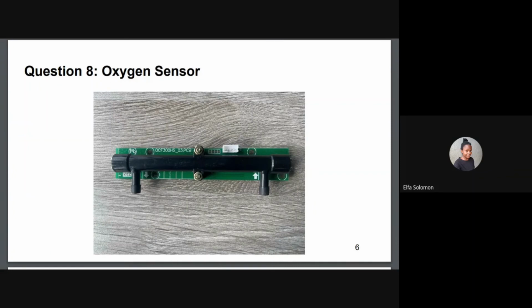That sounds like a sensor failure issue. As we know, oxygen concentrators have sensors installed in them to help enhance their performance and to detect failures within the concentrator. At the end of the oxygen generation system in a concentrator, just before the oxygen is delivered to the patient, there is a sensor, mostly an ultrasonic sensor. As you can see in the slide, that's the ultrasonic sensor. The function of this sensor is to monitor and measure the oxygen concentration of the air delivered to the patient, and it also measures the flow at which the oxygen is being delivered.